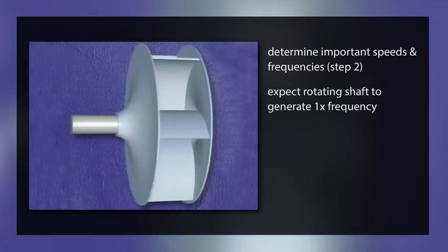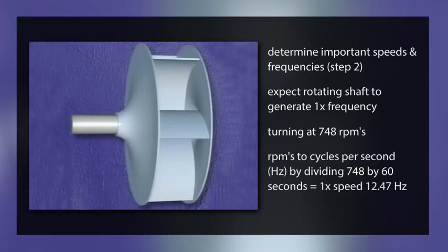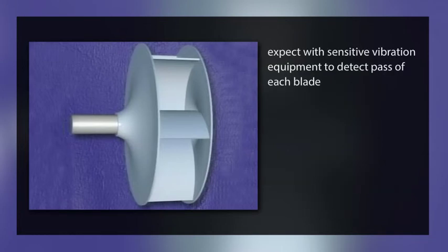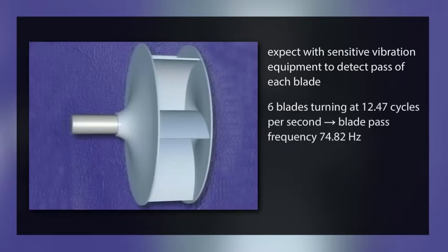Now let's determine the important speeds and frequencies — step two. We would expect the rotating shaft to generate a one-times frequency, and it is turning at 748 RPMs. We'll convert RPMs to cycles per second, or hertz, by dividing 748 by 60 seconds to get a one-times speed of 12.47 hertz. We would also expect, with sensitive vibration equipment, to detect the pass of each blade. Since there are six blades turning at 12.47 cycles per second, we could expect to find a blade pass frequency.